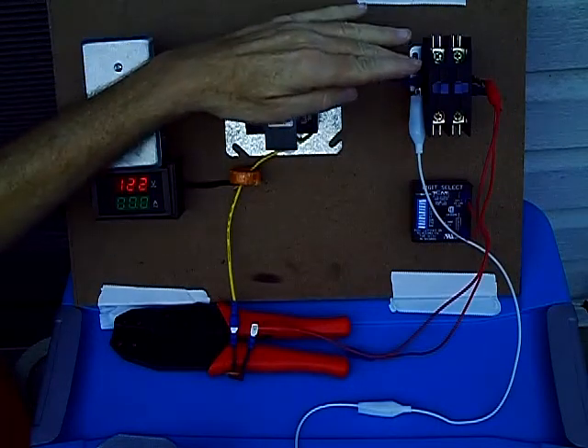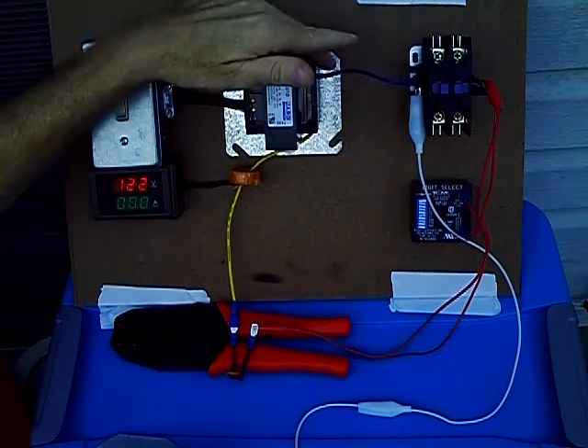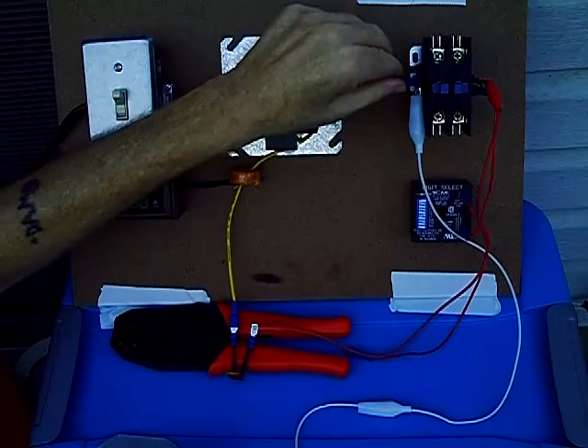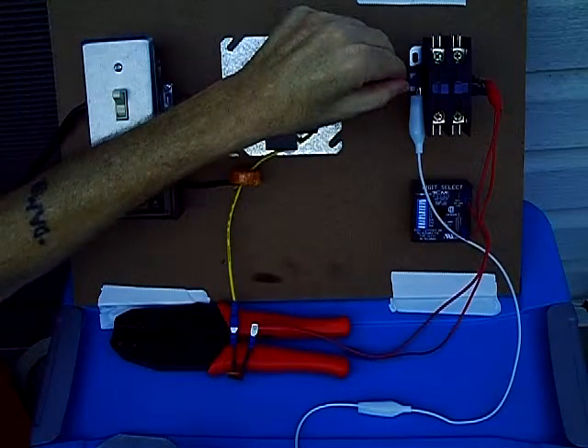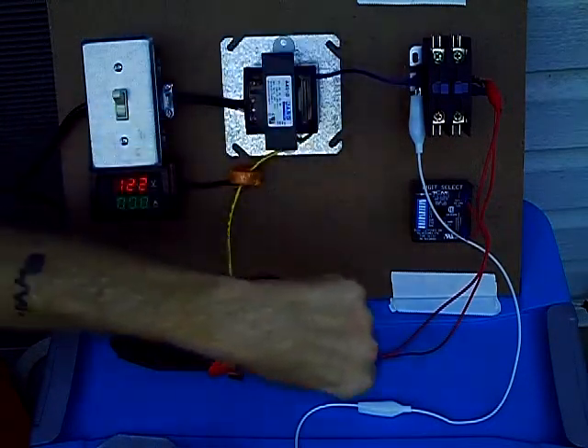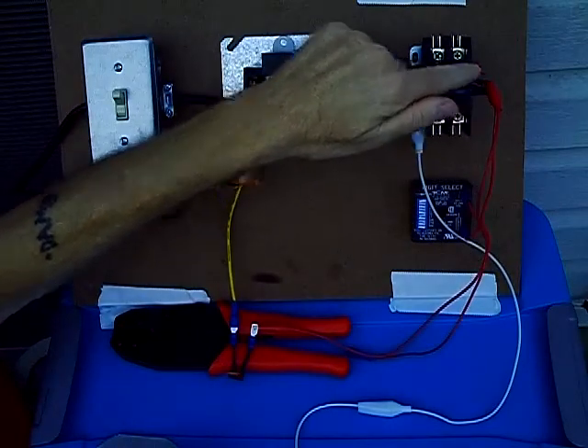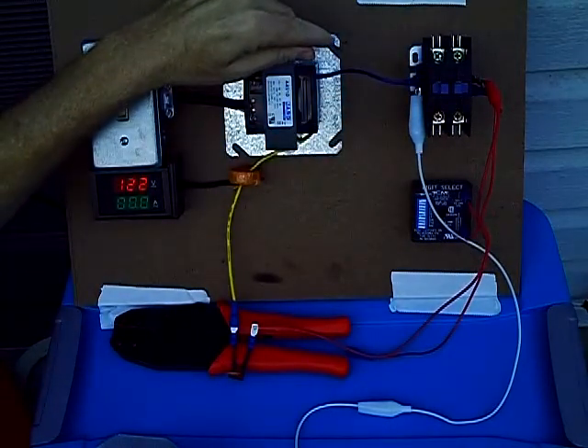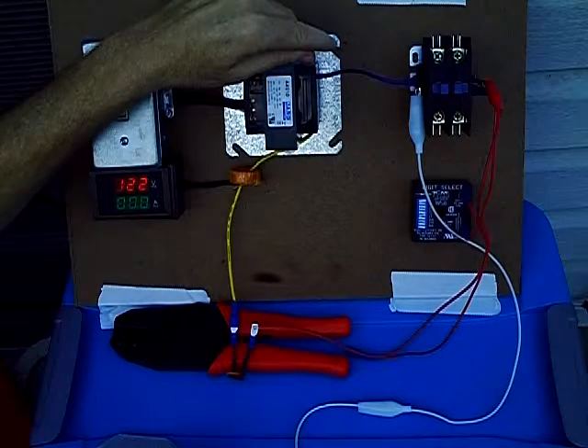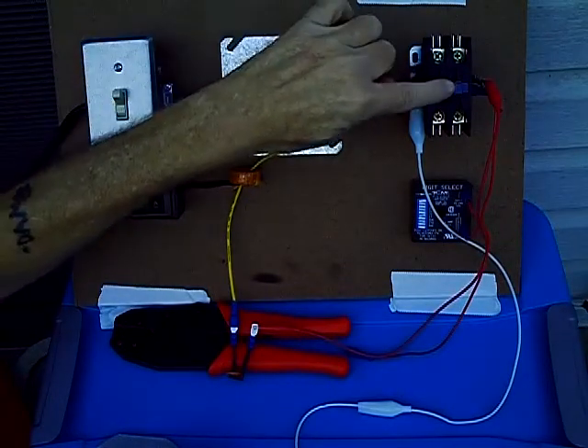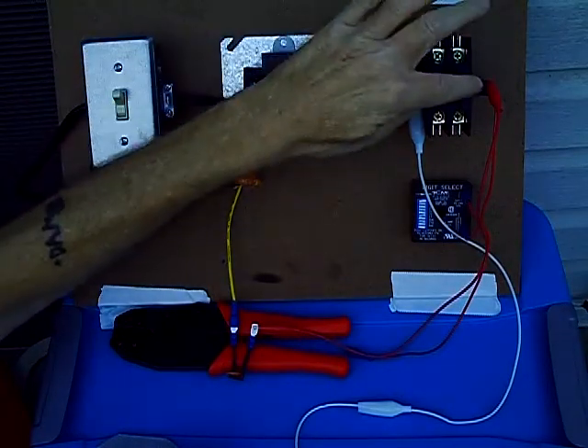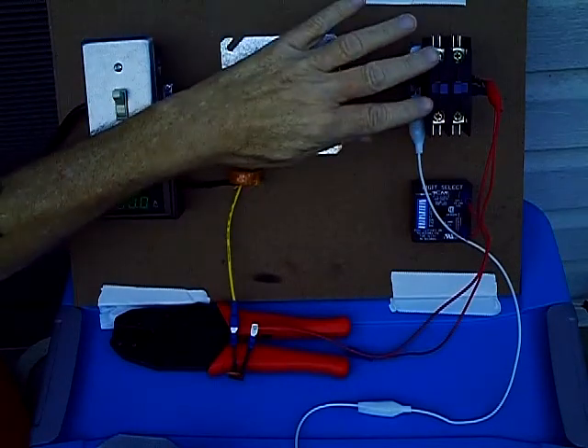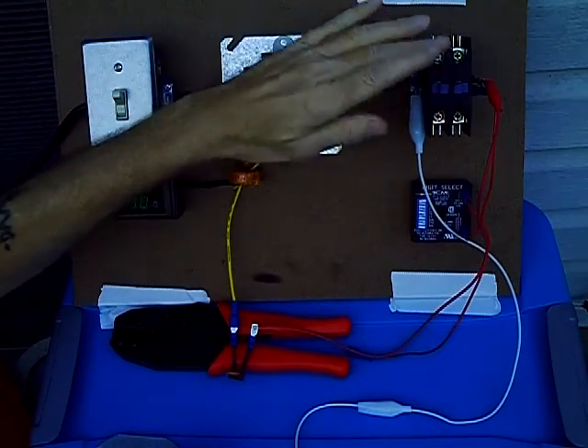The relay gets the other side of the power it needs straight from the transformer's other side. It goes to one side of the coil here, and the power going through the circuit energizes the other side of the coil. Anytime you have a 24 volt load like this coil and this contactor, it has to have both sides of the power to energize the coil in order for it to pull in and work.